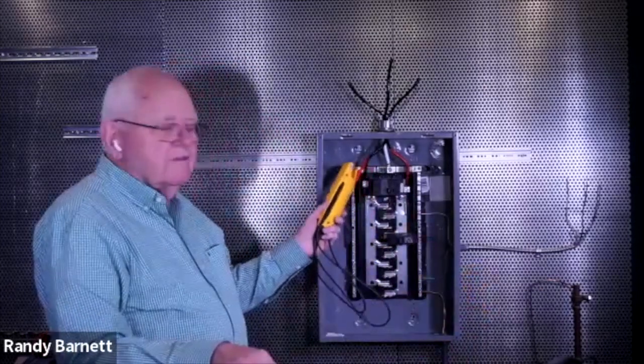Big system, obviously. Now, if we go over and look at sizing our grounded conductor coming in, and the main bonding jumper, the table says 2 or smaller, number 8 copper, everything looks pretty much the same until I get down to over 1100 kcmil. When I get down there, it says notes 1 and 2. Uh-oh, didn't give me a number then, does it? Note number 1 talks about this 12.5% rule. And so maybe you've heard of that. It says, okay, if we're larger than 1100 kcmil, copper, the grounded conductor or bonding jumper shall have an area not less than 12.5% of the area of the largest ungrounded supply conductor or equivalent parallel conductor.